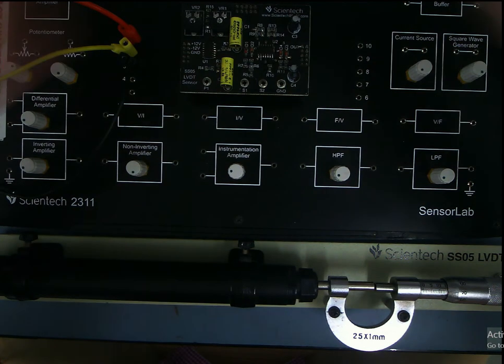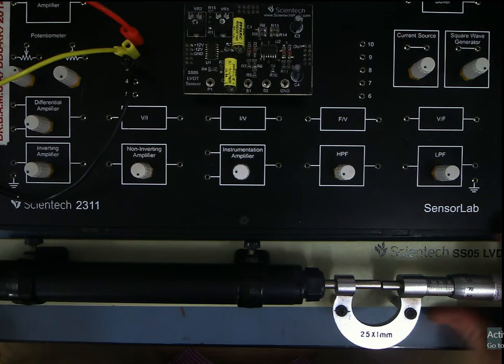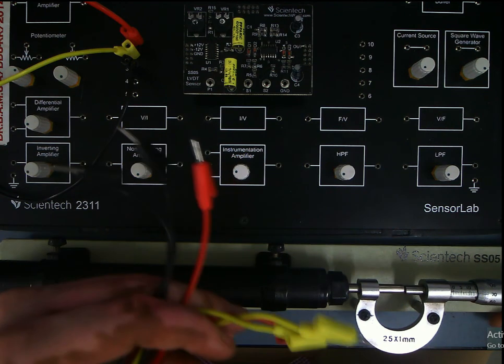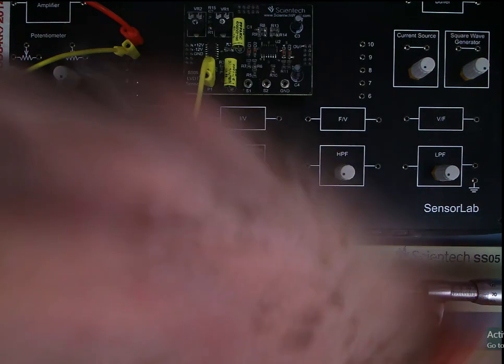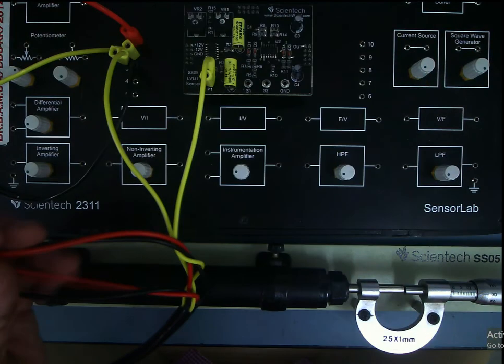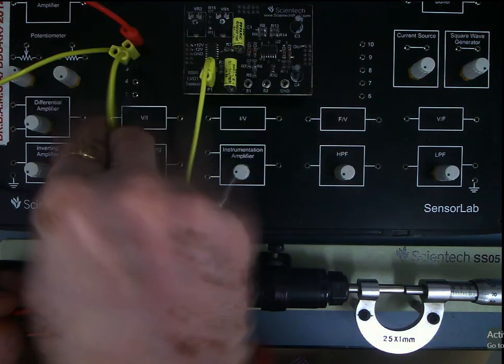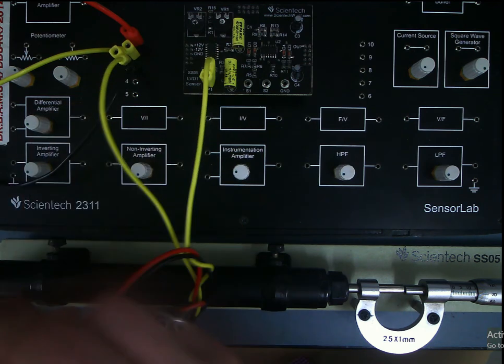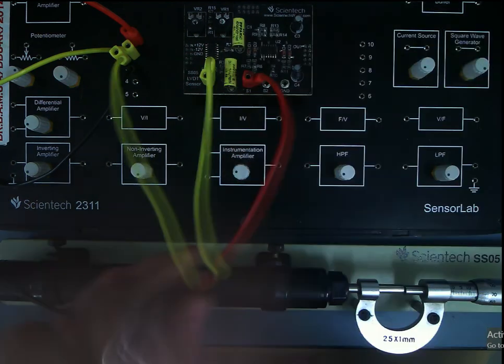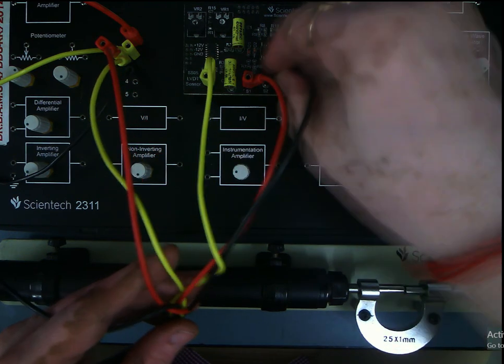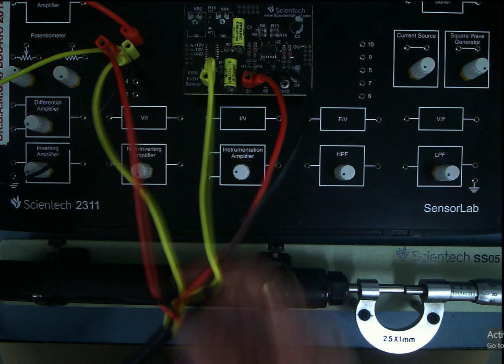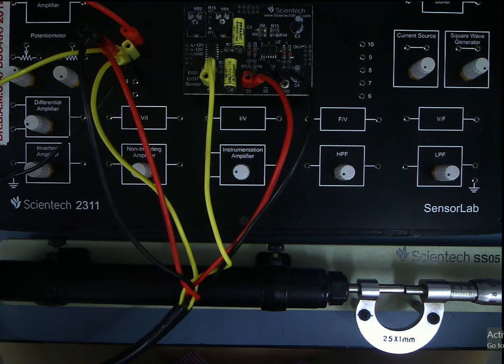Okay, so now we can find these are the terminals of the LVDT. This yellow terminal is meant for the primary. I'm connecting one of the terminals to primary P1 and the other terminal to ground, this black terminal. Then one of the secondary terminals is connected to S1, and the other terminal is again connected to ground. The other winding is secondary S2, and its other terminal goes to ground. So that's all about the connection.